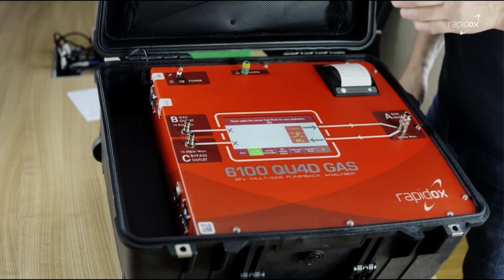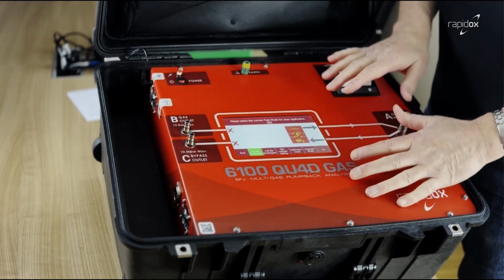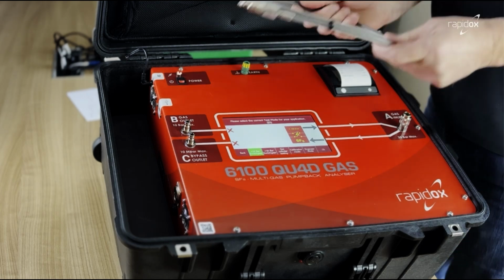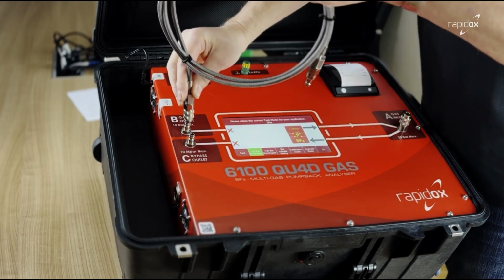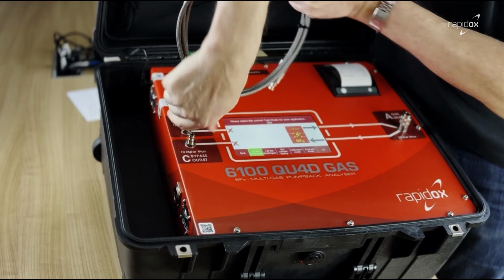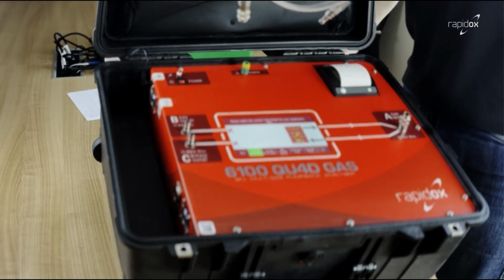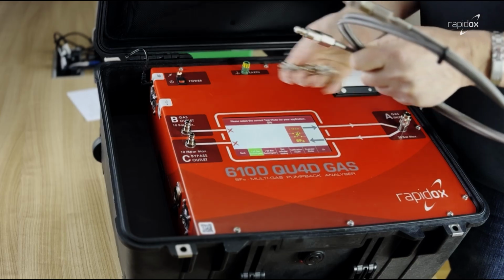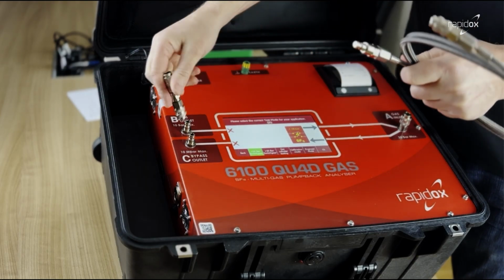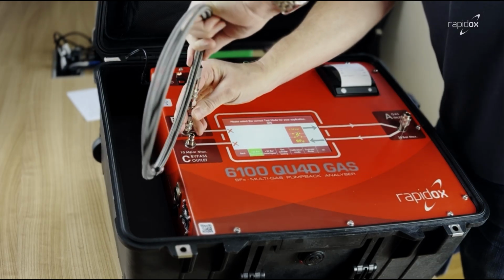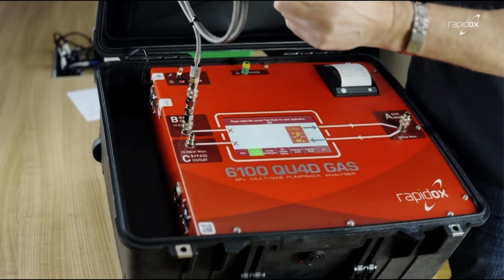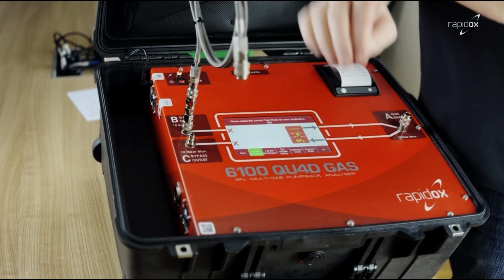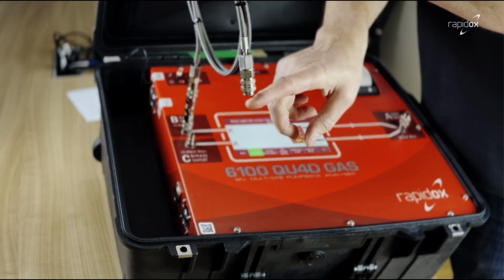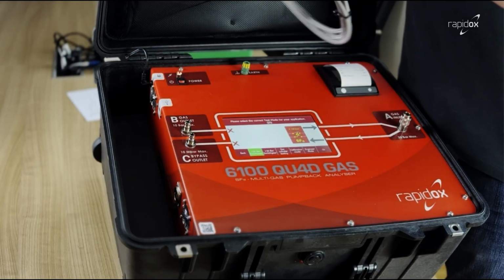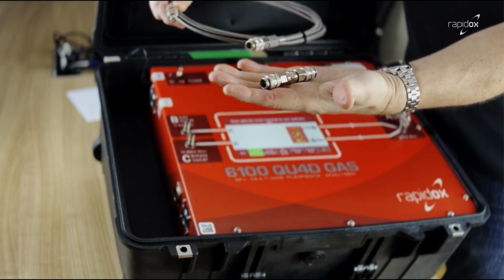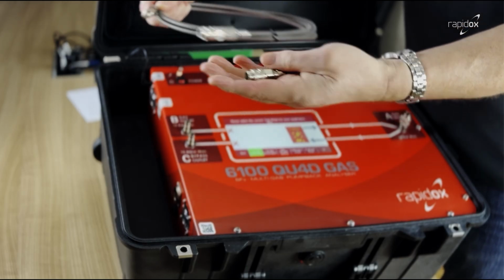If you don't want to use that accessory, or you've lost it, or you are going to be pumping into a canister, then it is possible to use this hose as well, because this hose will also fit onto port B, as you can see. However, if you're going to be working with a gas recovery bag, it's likely that you'll need a gender changer, and this is our gender changer, and this simply fits on there like that, and then you can attach the male side of the fitting, and then you now have a female side which will successfully connect to your gas recovery bag, which normally has a male Dilo Rectus fitting on it. So the gender changer is a standard accessory that we supply. Together with these pieces of accessories, it's possible to have any combination of hose attached to any port.